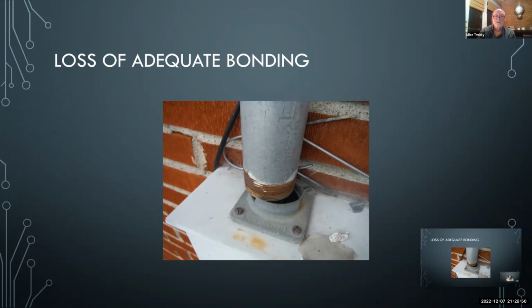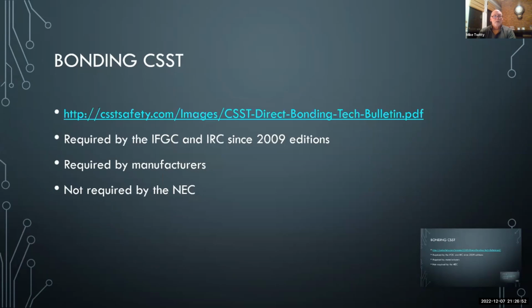Most of them you're seeing these days are using PVC, but we'll touch on CSST. We're not going to go into detail on that. I'm sure you guys are aware of that. This is the link for the bulletin. It's been required to bond the CSST in the International Fuel Gas Code and IRC since the 2009 editions, and it's required by manufacturers. It is not required by the NEC as far as the specific bonding requirements with the number 6 conductor, so on and so forth, that the others require.